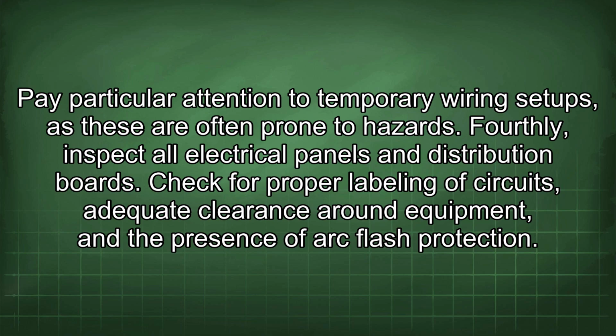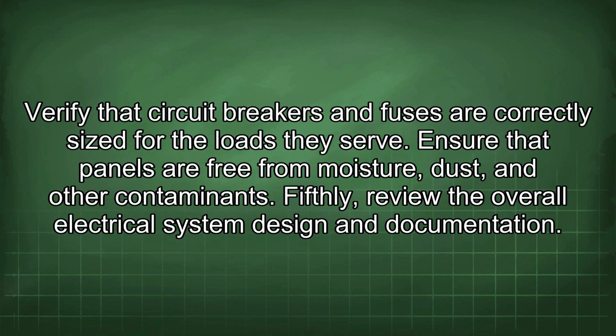Fourthly, inspect all electrical panels and distribution boards. Check for proper labeling of circuits, adequate clearance around equipment, and the presence of arc flash protection. Verify that circuit breakers and fuses are correctly sized for the loads they serve. Ensure that panels are free from moisture, dust, and other contaminants.